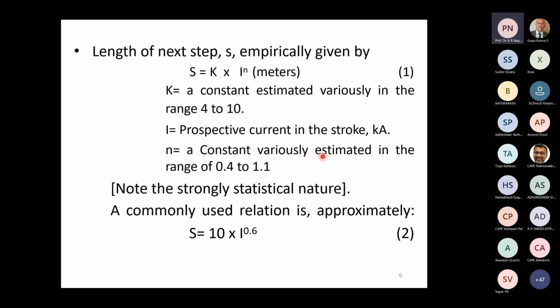It varies in the range of 0.4 to 1.1. Please note again the strongly statistical nature. So if you find that a given aerial system did not give 100% protection, it did give, let me say as an example, for a few years, no problem at all. Suddenly one year, there is damage caused, even though the aerial protection system has been provided.